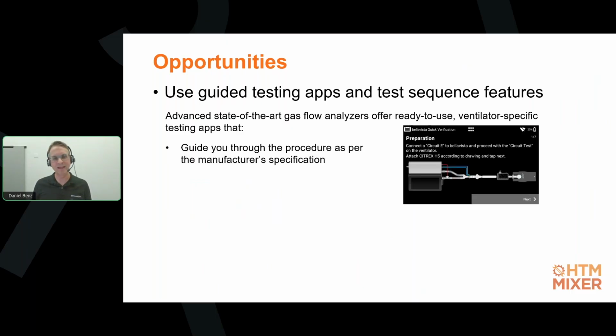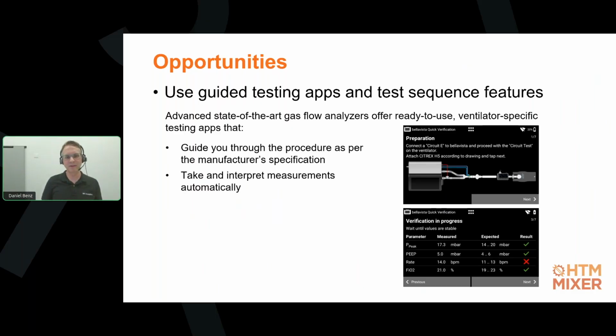They can guide you, first of all, through the whole procedure. They can show you how you have to set up your ventilator, like in this screenshot you can see here, and your gas flow analyzer. Then they take and interpret measurements automatically. Because it's like a coded version of the service manual, it knows what measurements we have to take, and it can calculate the ranges and give you pass-fail results right there on the screen.